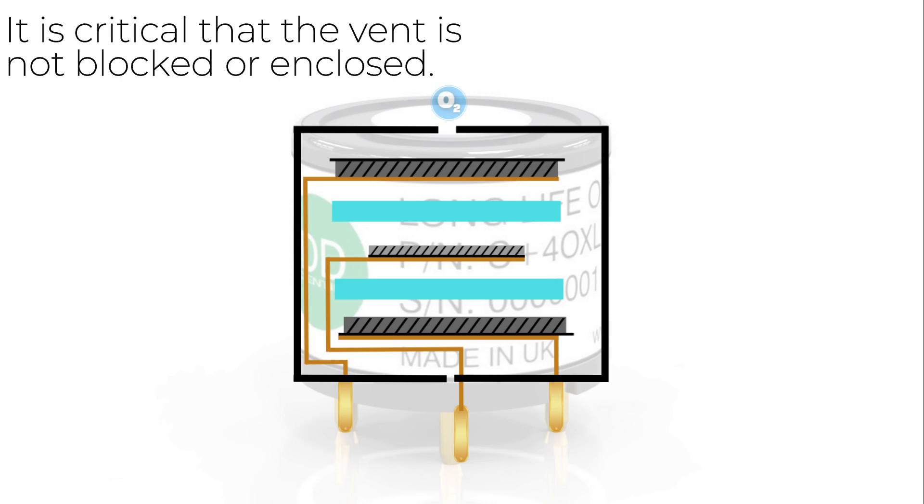As previously mentioned the vent must be kept clear during use or oxygen will build up inside the sensor, swamp the sensing electrode and provide enhanced and inaccurate signals.